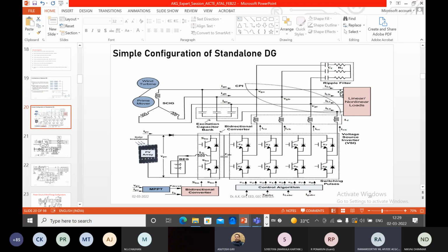In the previous case, you are not taking any difference for the generator source current, you are taking only load current. But now for generation, if you are calculating the reference current for the generator, you will take the load current minus these currents, or you can say supply current from the PV. That's why this will be the change during control.